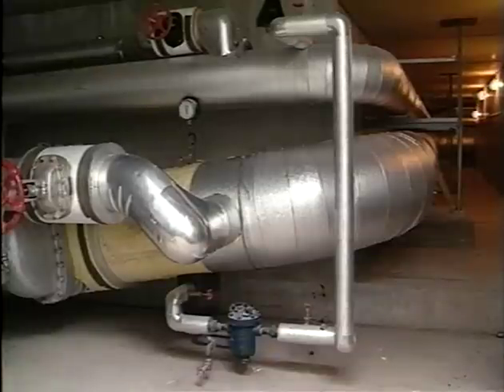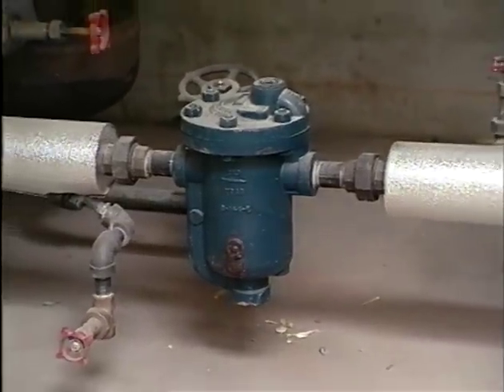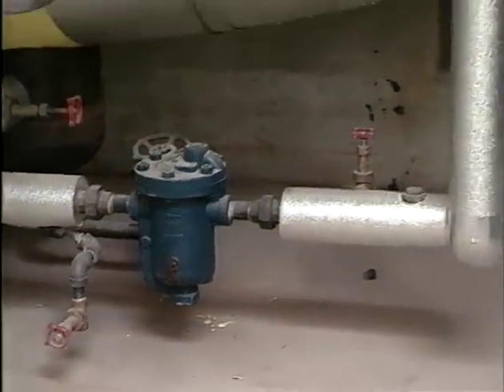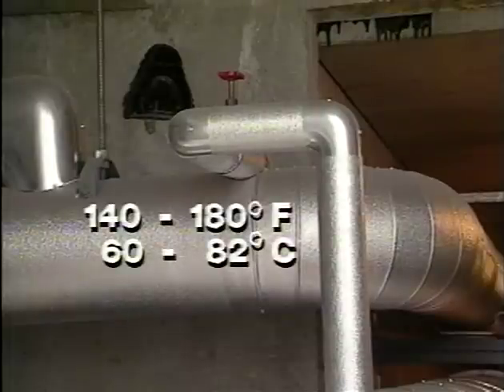One likely place for thermal shock to occur is in steam utility corridors. In these areas, the drip traps from high-pressure steam mains often discharge directly into the pumped condensate return lines. The temperature of the condensate in these lines usually ranges from 140 to 180 degrees Fahrenheit.